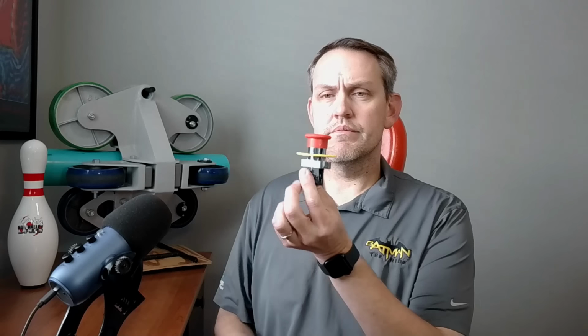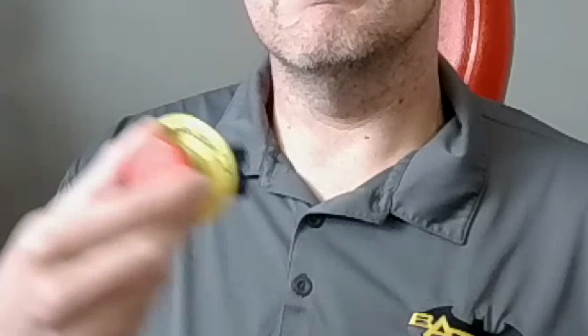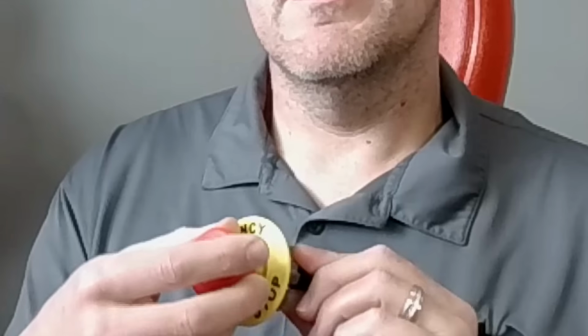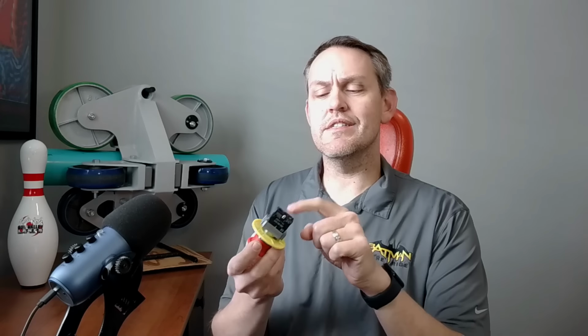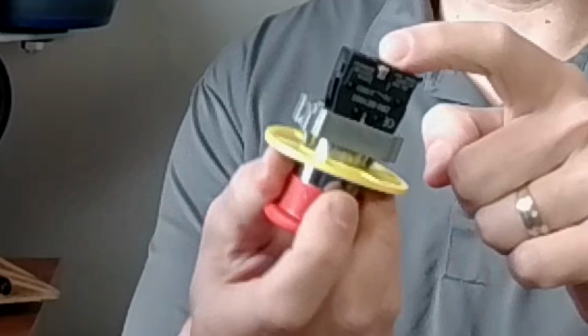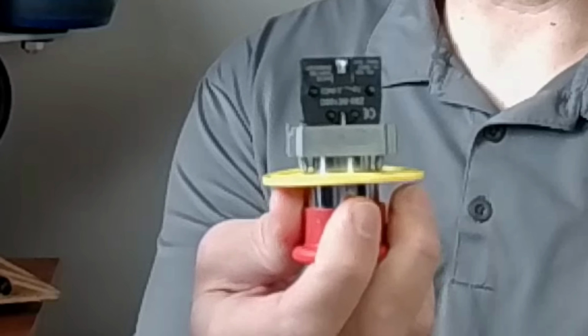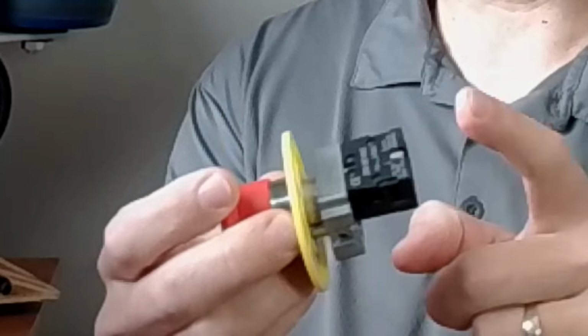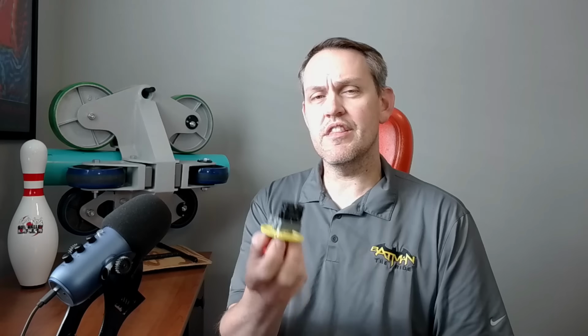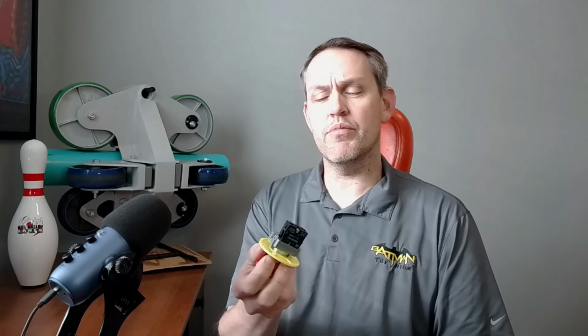When I was purchasing buttons for rides, because you'd have to do it from time to time, a lot of times what goes bad is underneath the button, the contact block. Right here, here's an e-stop, emergency stop, right? This is the part you push on, but the part that actually does the electrical work is this little black guy right here. This little guy does the actual opening or closing of the circuit to make the button function. So this is what's called a contact block.